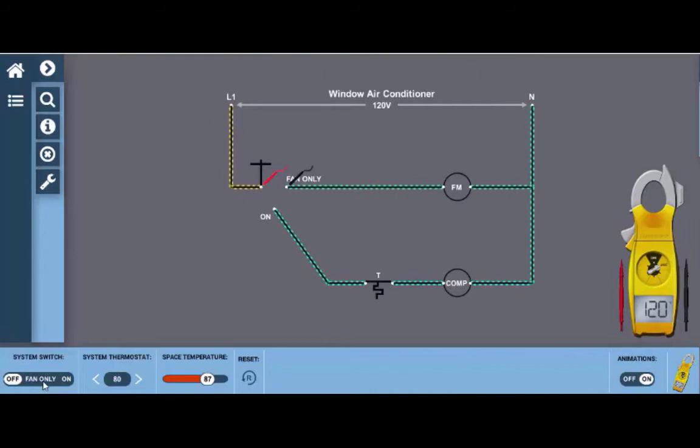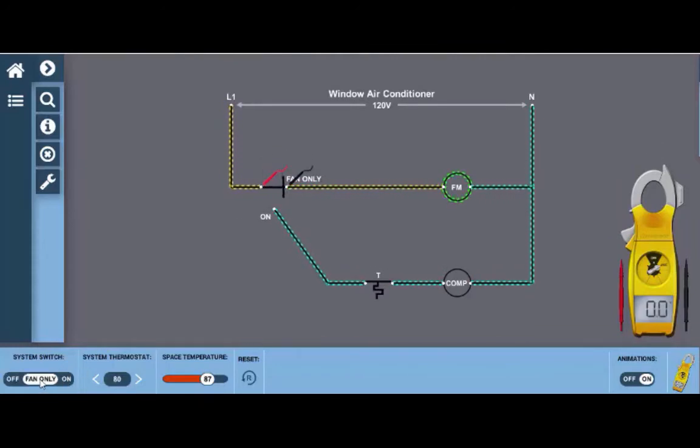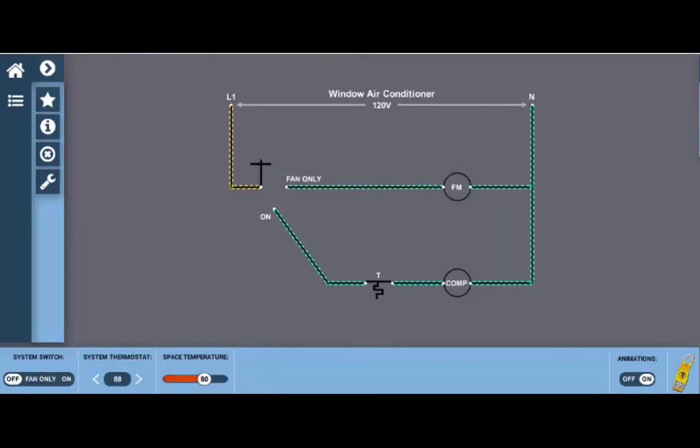Now again, if we close the fan switch we should have 120 here and 120 here which would mean there would be a difference of zero. So let's see what happens. We click fan only and there we go we can see that we've got zero volts of potential there.